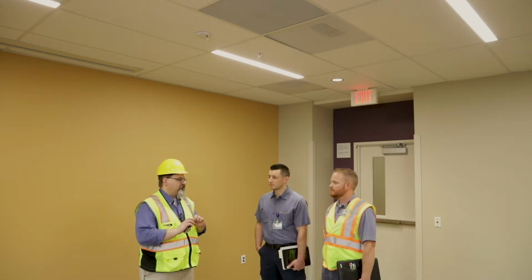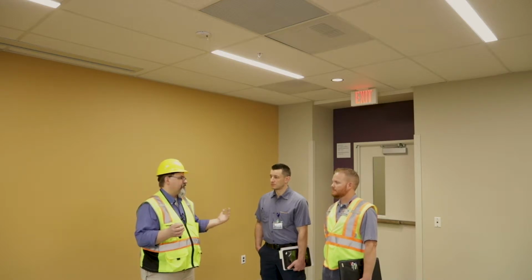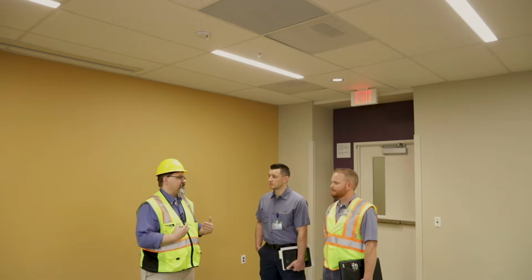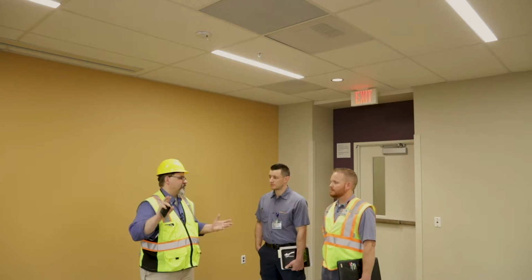Now, if there are two Cat5s in there, and this is on a daisy chain of devices, if we unplug one of those, then some of the other devices might not be responsive either, because the switches and the sensors actually receive power across the Cat5, 24 volts from the room controller. Good question, because it points out something I need to point out to you as far as troubleshooting.